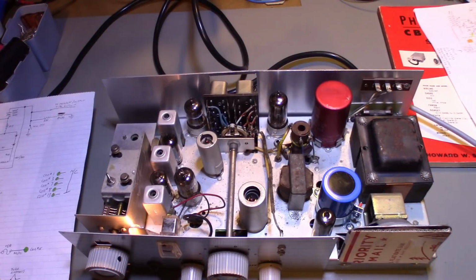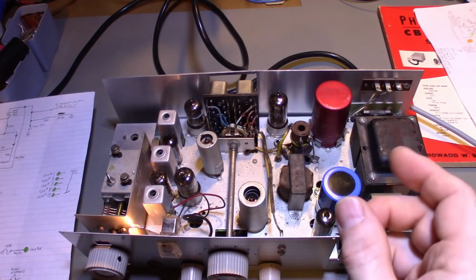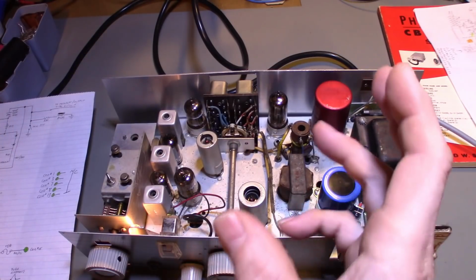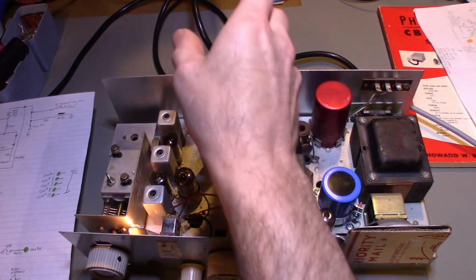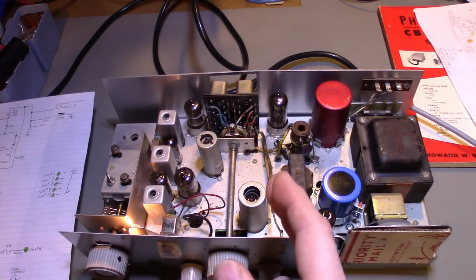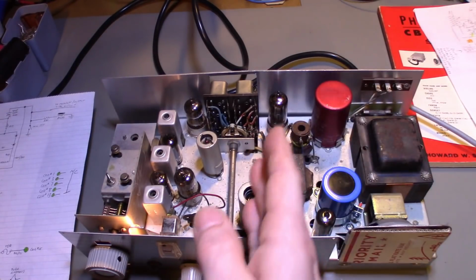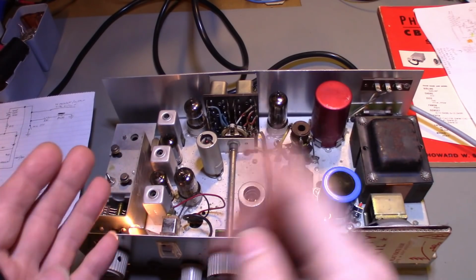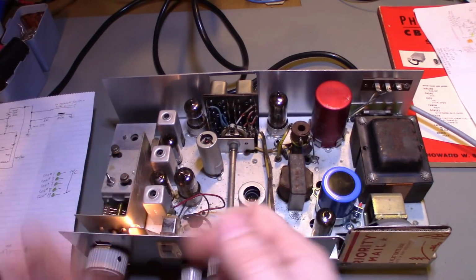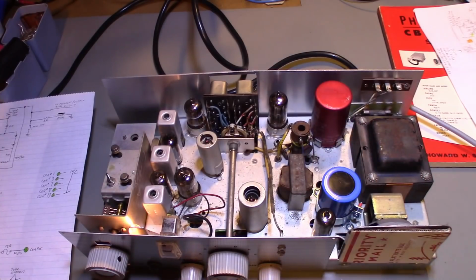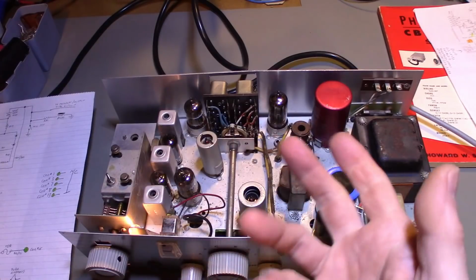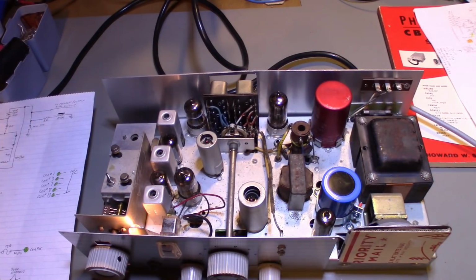All it is, is a light bulb, literally just a light bulb like you'd screw into your ceiling. But it needs to be an old style incandescent bulb, 120 volt. The advantage of using a light bulb is that only so much current can pass through it. Whatever you put in series with it, no more current can flow than it would normally draw wired direct to the AC line. So the filament acts as a current limiting device, and it works really well, and it's cheap. All you need is a socket, a plug, a light bulb, and some wire. That's your current limiting device.